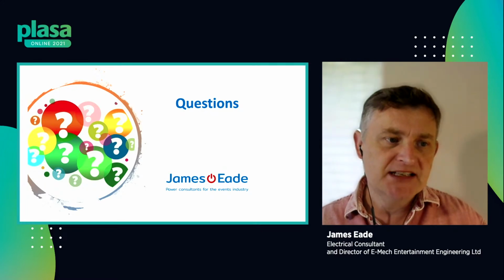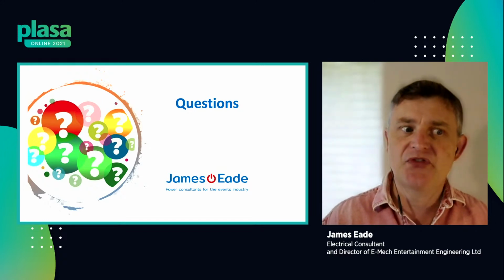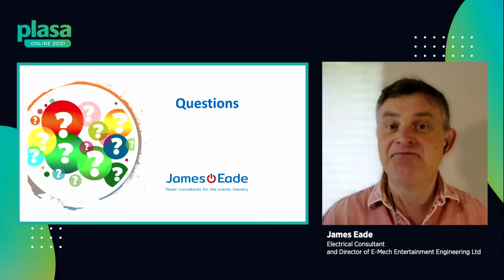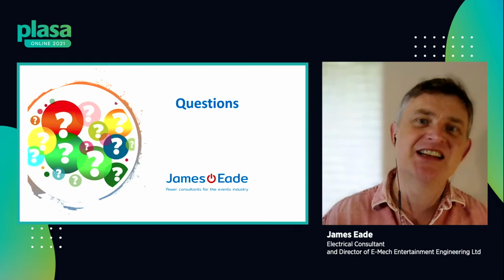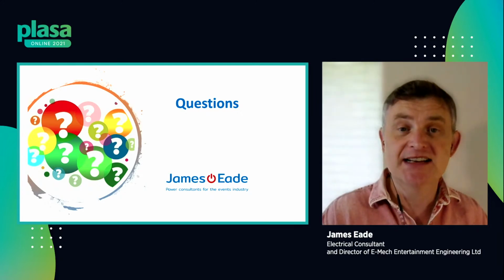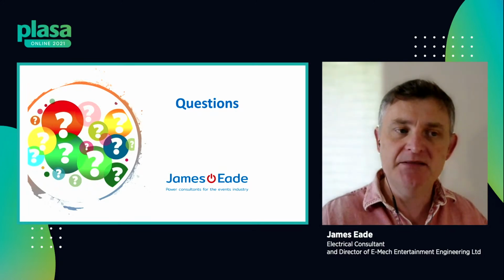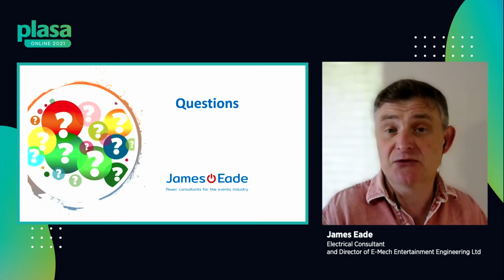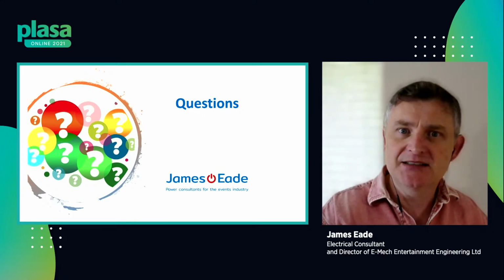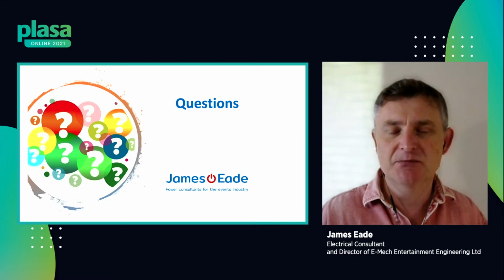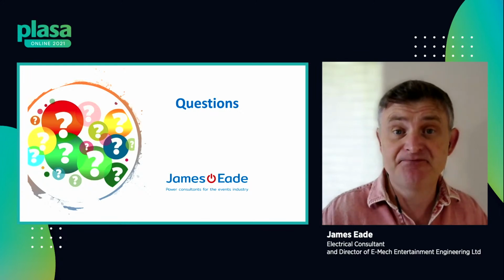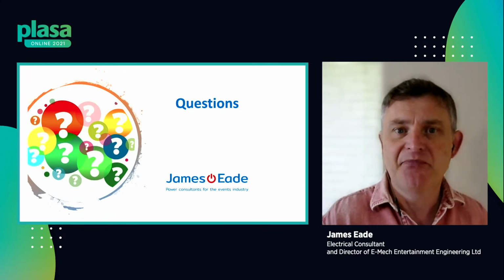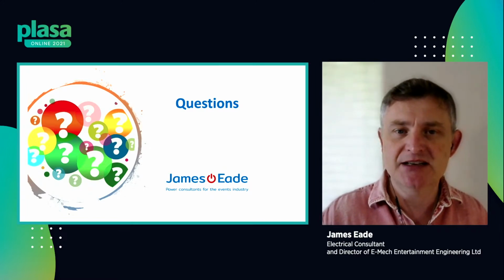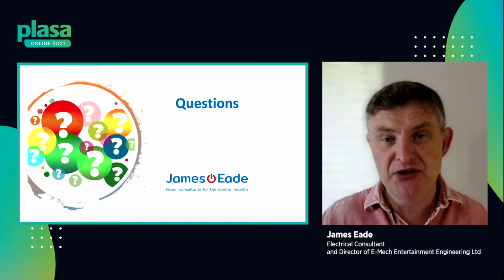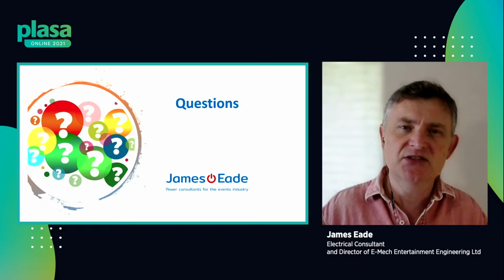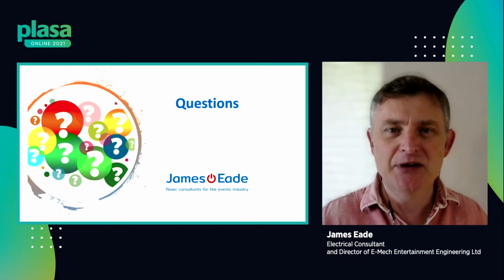Interested in earthing or otherwise of generators for outdoor gigs, from Ruth - we haven't really got time for that in this session. I have written a very good book on the subject. If you look for the practitioner's guide available from the IET, that's got the latest generator earthing guidance in it. The original book I wrote was based on the Code of Practice for Earthing, BS7430, but over time it's been accepted that the guidance in that wasn't 100%. So what we've done is revisited this in the UK and come up with more reliable, better engineered solutions to generator earthing - when you do need to earth them, when you can get away without putting an electrode down, and when you do need one, etc. It's a bit more involved than I can cover without drawing pretty pictures, I'm afraid.